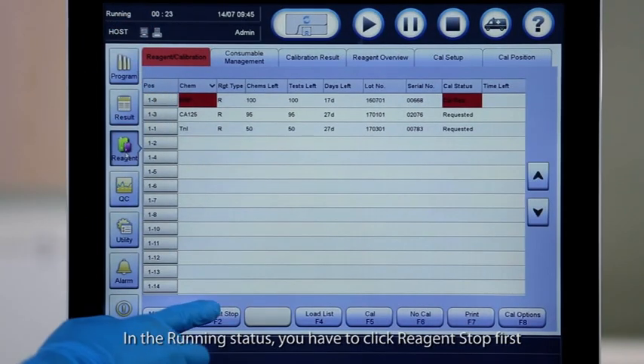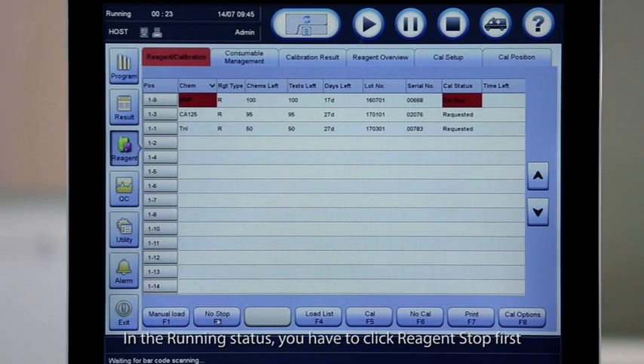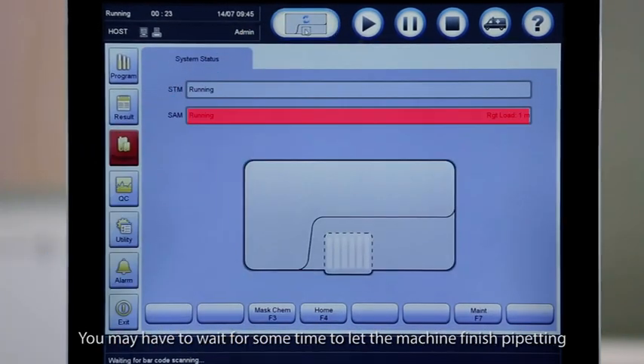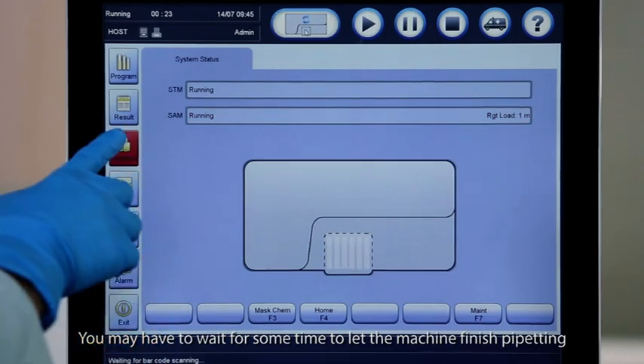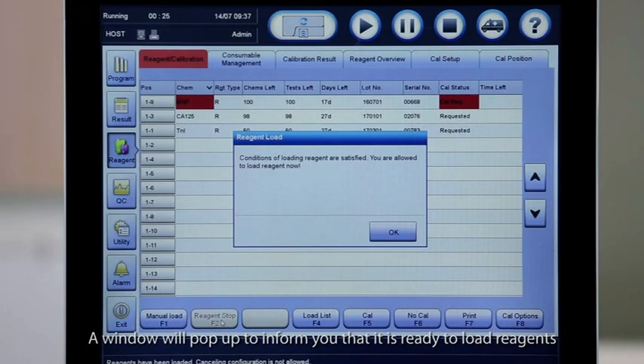In the running status, you have to click reagent stop first. You may have to wait some time to let the machine finish pipetting. A window will pop up to inform you that it is ready to load reagents.